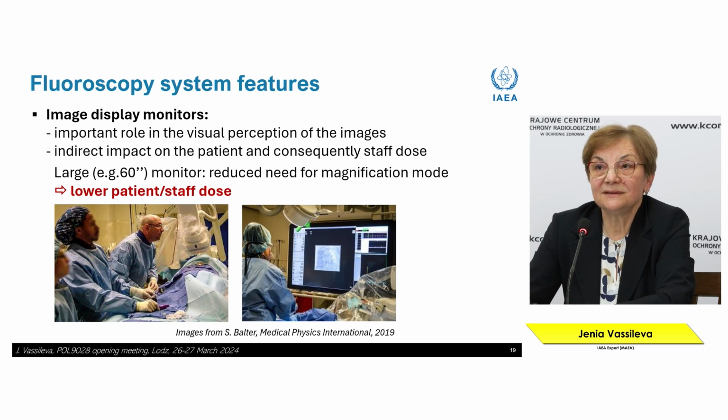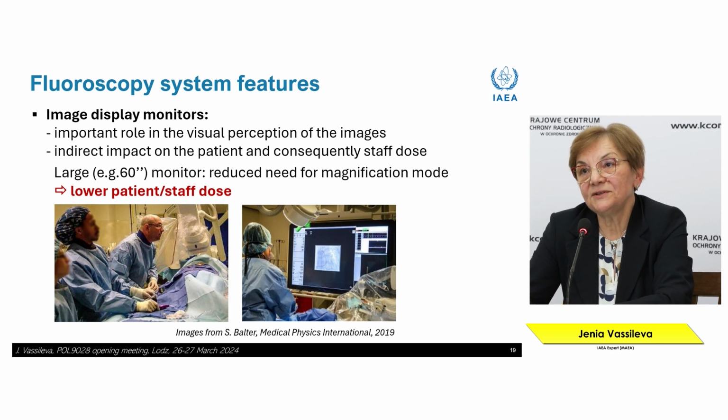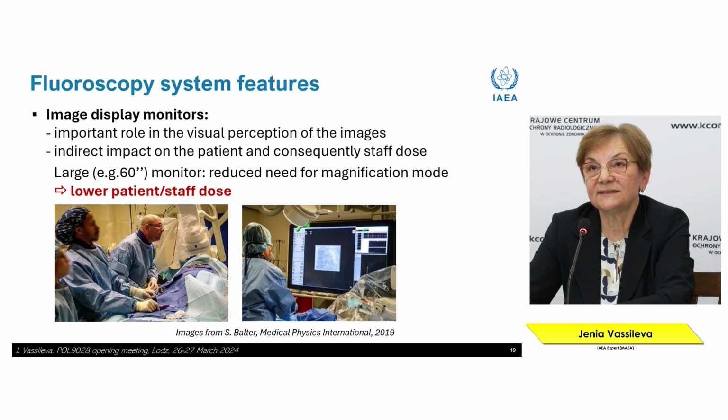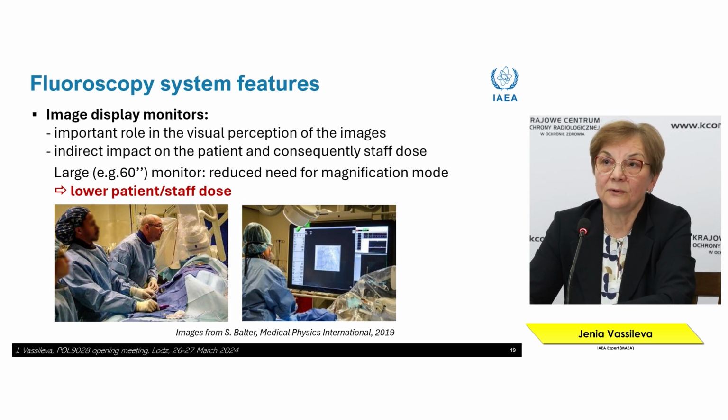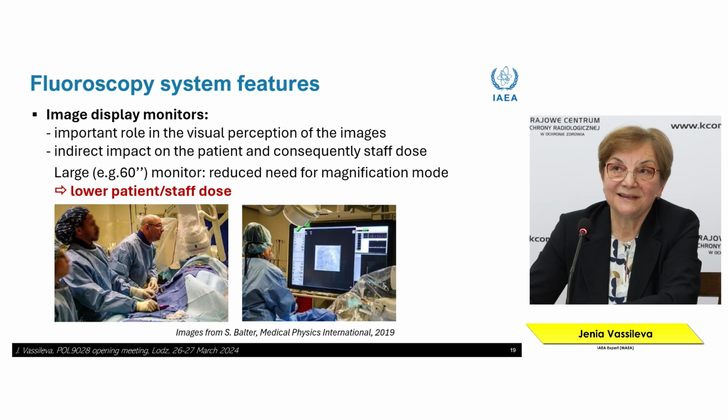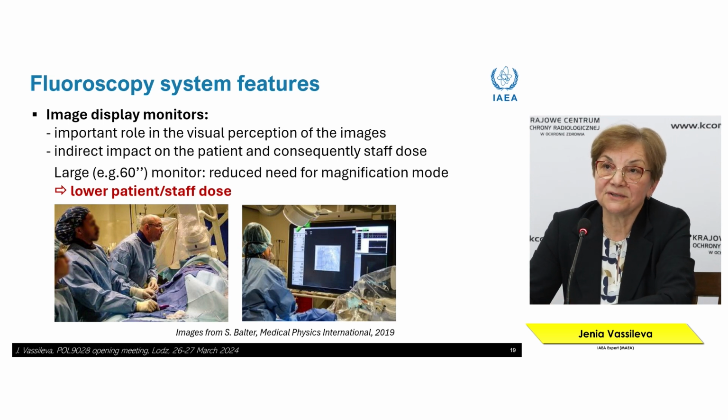In modern interventional departments, large screens are used. One may ask, what is the influence of the screen on the patient and staff dose? There is influence, because using these large screens, there is less need to use magnification mode. Using less magnification, as I have shown, is linked to decreasing dose to the patient and dose to the staff.